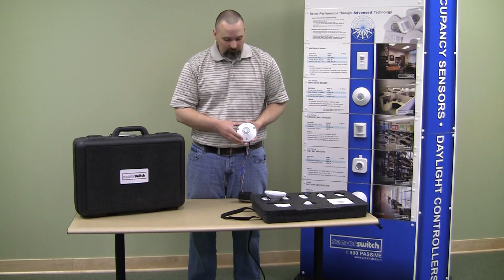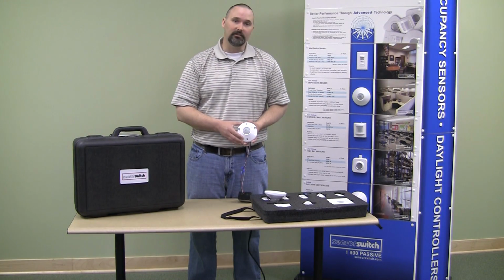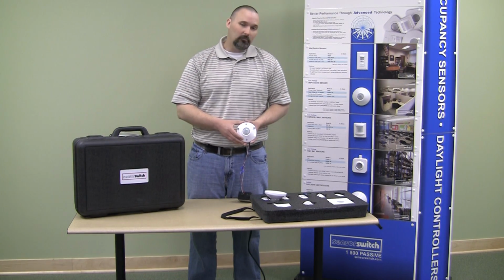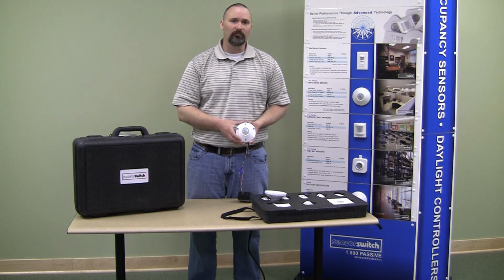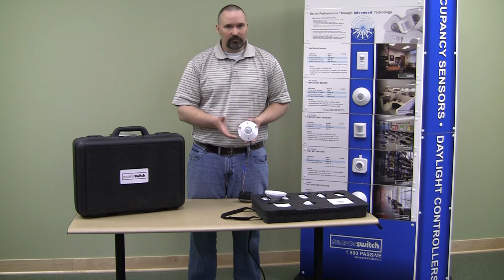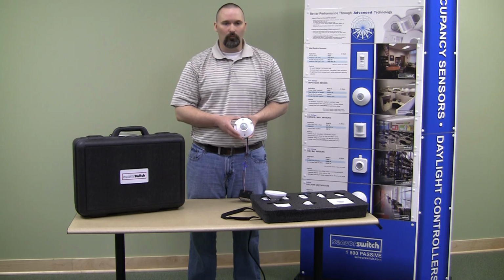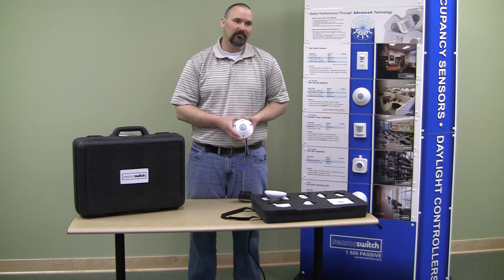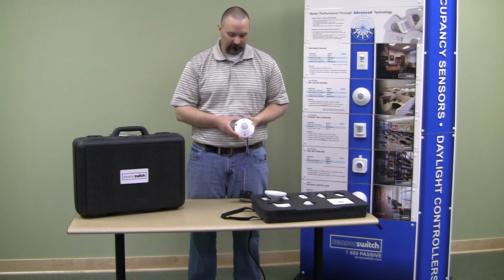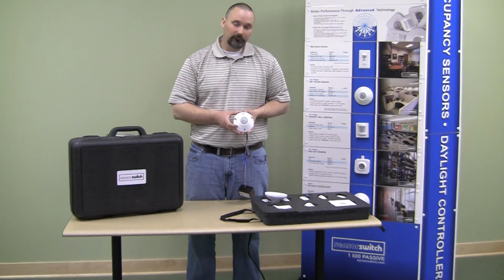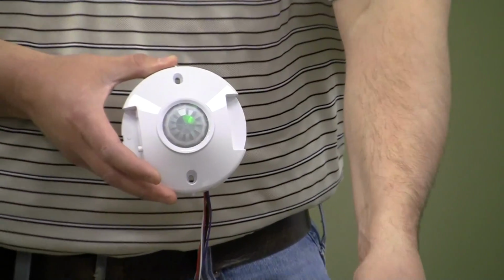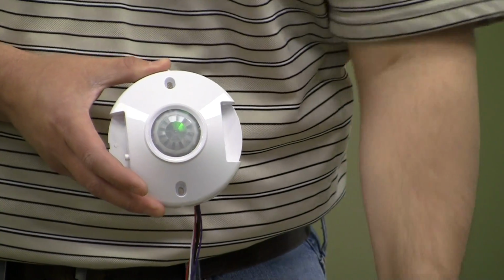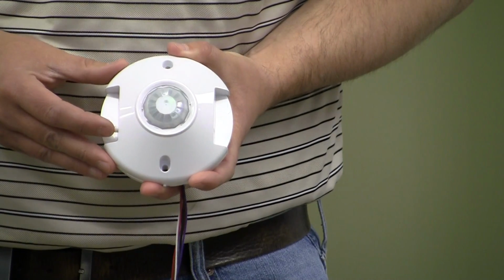The other thing that we can do with this occupancy sensor is adjust the time delay and put it into a test mode. What we use test mode for is to just ensure that the occupancy sensor will actually time out, and we use it for training or testing purposes. To enter into the test mode, once again, that's listed on our cover on the inside of the beauty ring. To enter it, you push it 4 times.